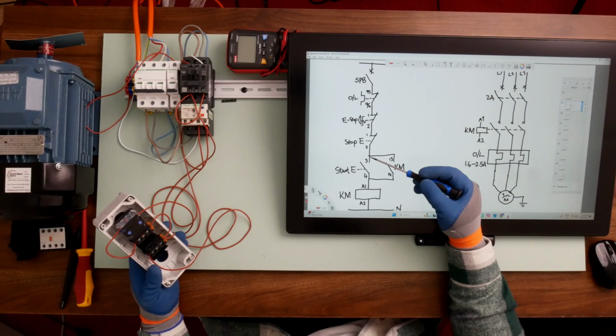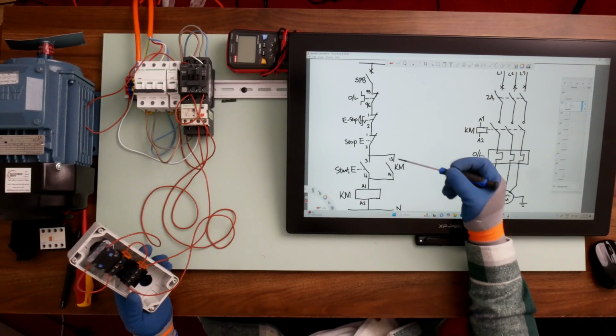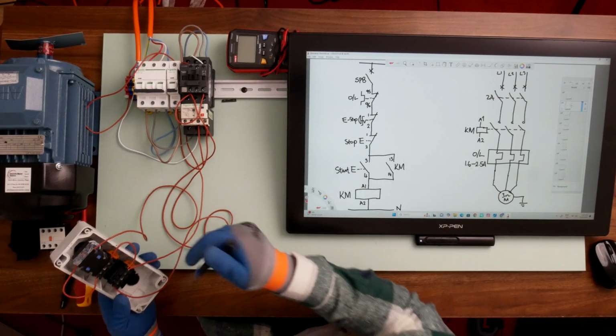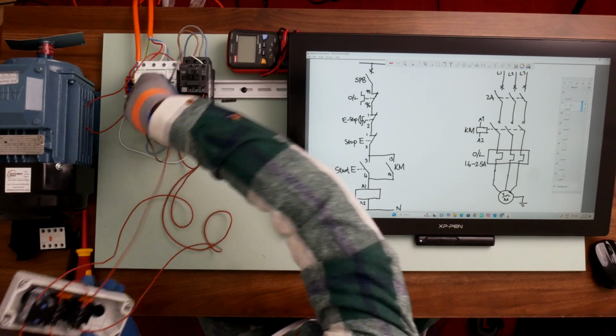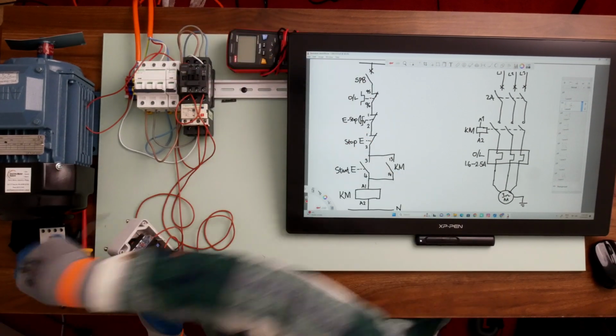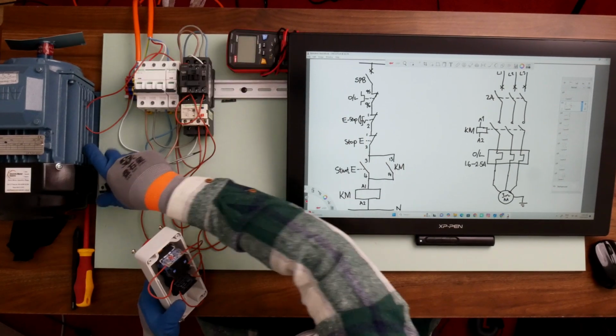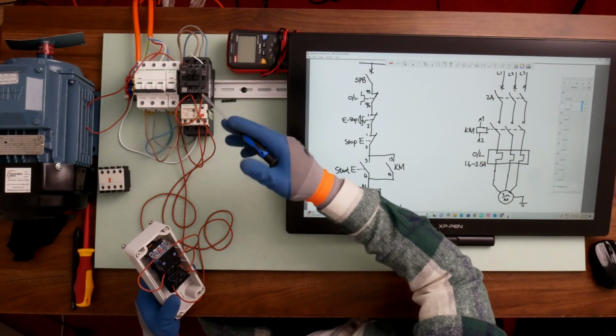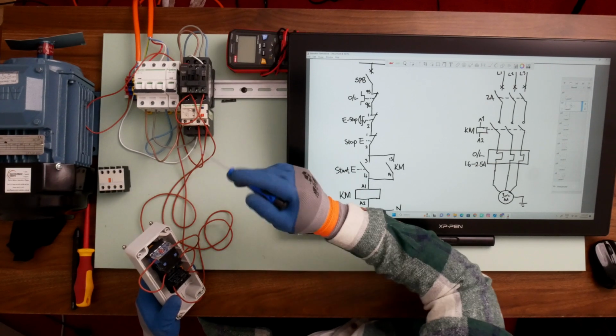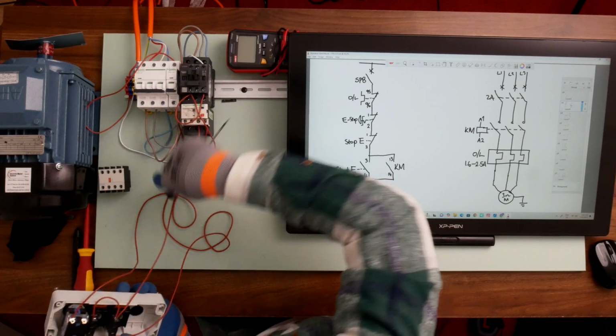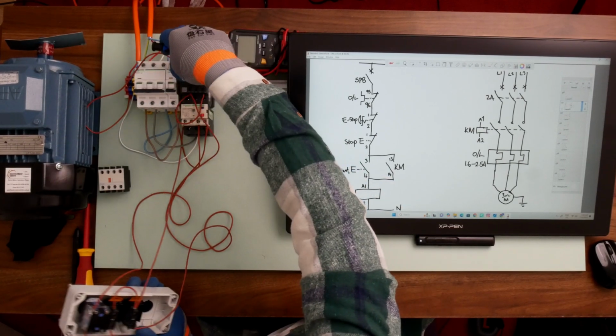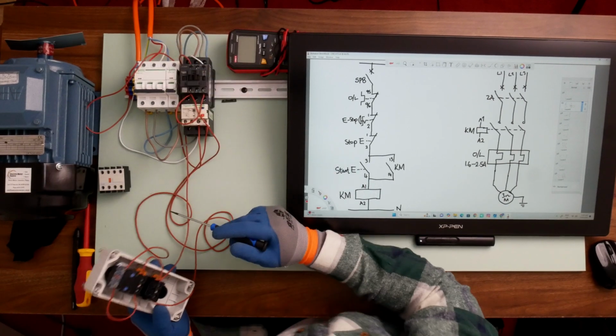So to the top of the start button, it's linked here. Then I have a long lead which connects 3 to 13. So from 3 on my start button, it goes straight to 13 here on my auxiliary contact. And remember, I didn't have to use this clip-on auxiliary contact, because my contactor already has auxiliary contacts here. So I just need one set of normally open contacts for this simple direct online starter. So from start here, I have this long wire going to 13 here. I've tucked it underneath over there to reduce the spaghetti here.